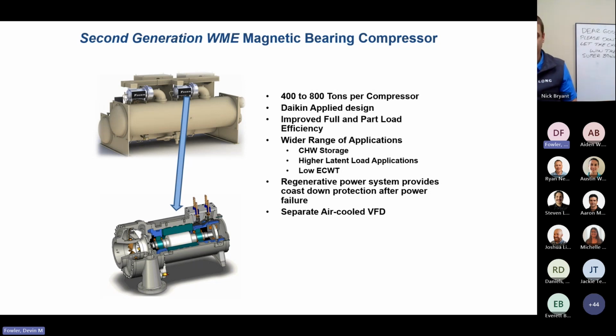We're able to offer improved full and part load efficiencies when compared to an oiled centrifugal chiller. We have a wider range of applications, can use these for chilled water storage, high latent load applications, as well as low entering condenser water temperature applications.